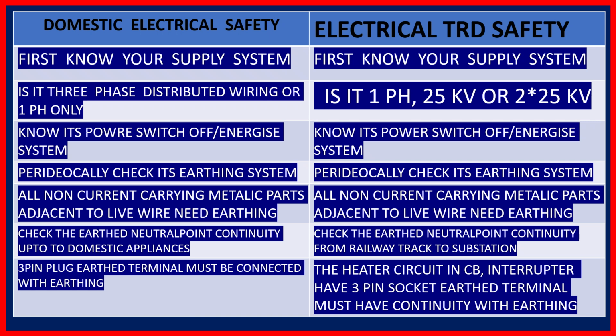So all non-current carrying metallic parts, in both cases, we are connecting with the earth. Then this neutral point is also earthed. Check the neutral point if it is continuous with the earth connection. If it is continuous, from your home to every portion of the building, you check if you get continuity.